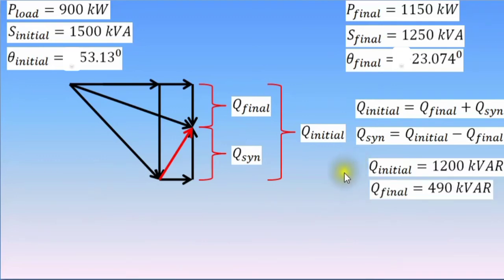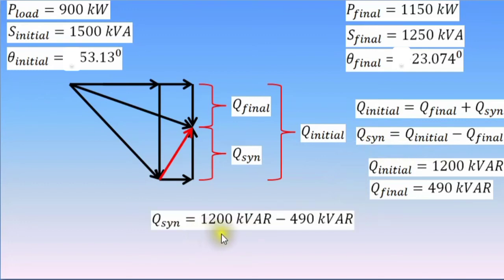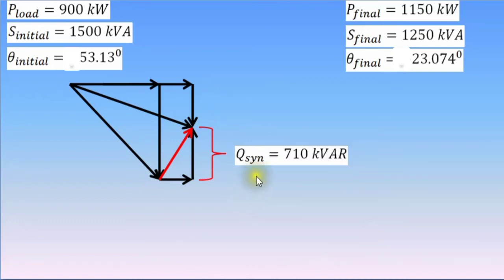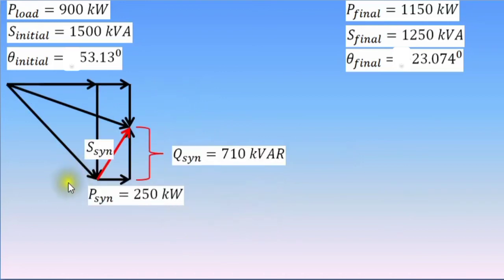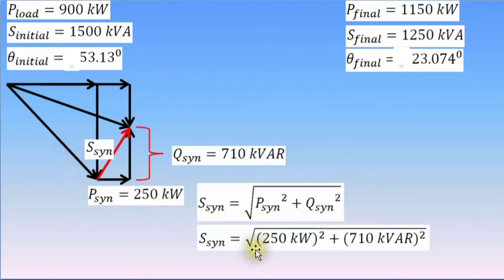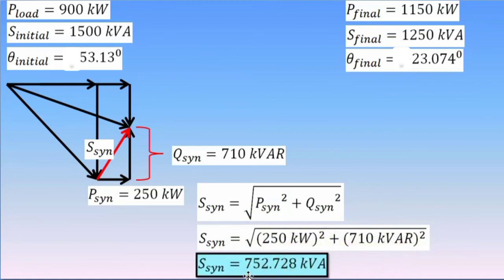Now that we have the values for the initial and final reactive powers, we could substitute them to this equation to determine the reactive power input of the synchronous motor. 1,200 kVAR minus 490 kVAR, this is 710 kVAR. This is the reactive power input of the synchronous motor. Since its effective power is already given, that is 250 kilowatts, we can now determine by using the Pythagorean theorem its apparent power. Again, from this formula, substitute the values. The square root of 250 kilowatts squared plus 710 kVAR squared, this is 752.728 kVA. So this is the kVA input of the synchronous motor.